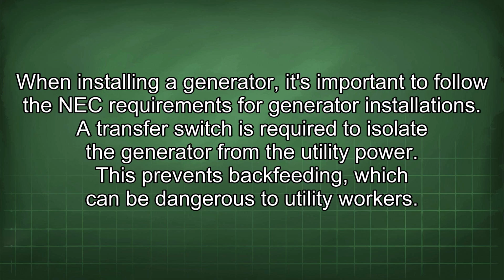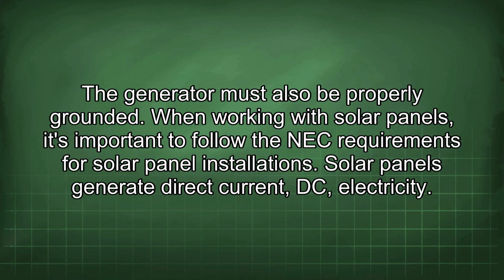When installing a generator, it's important to follow the NEC requirements for generator installations. A transfer switch is required to isolate the generator from the utility power. This prevents backfeeding, which can be dangerous to utility workers. The generator must also be properly grounded.